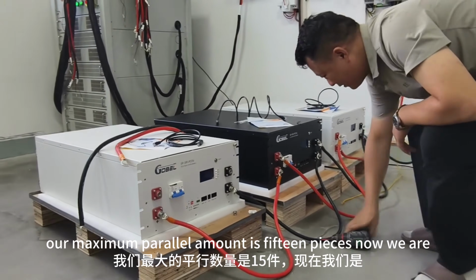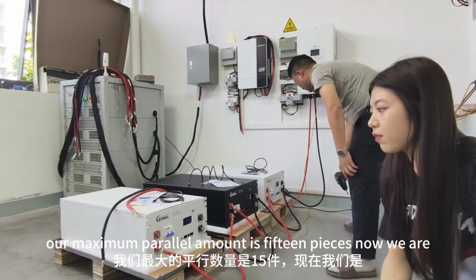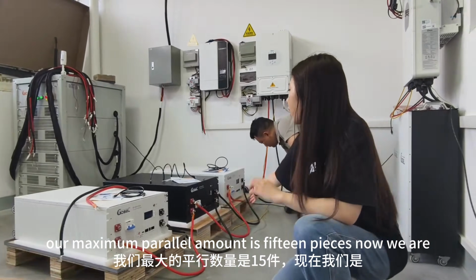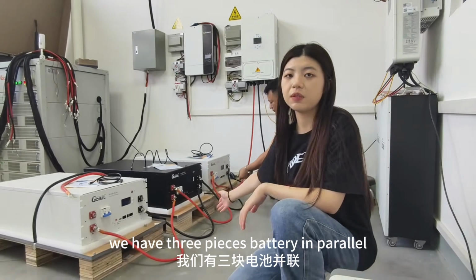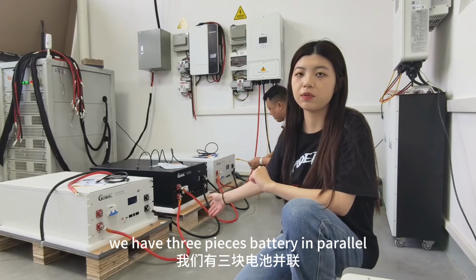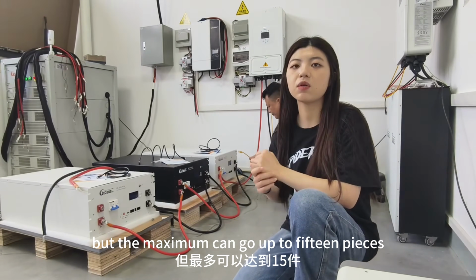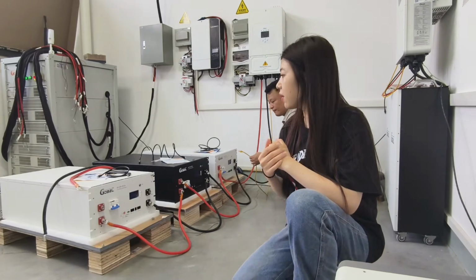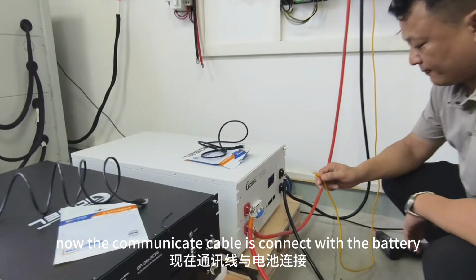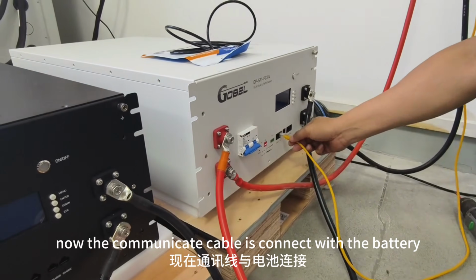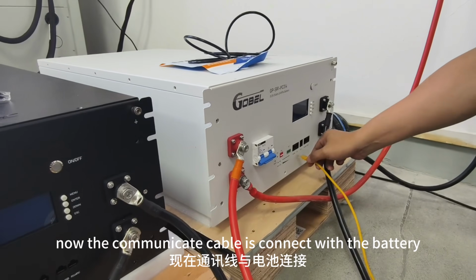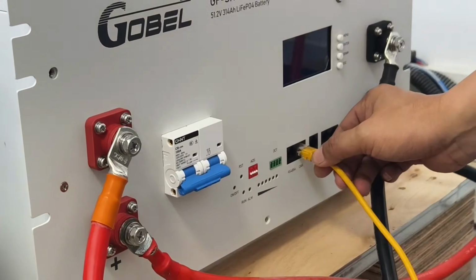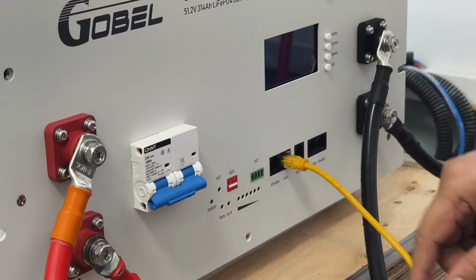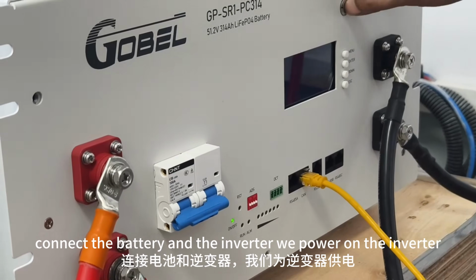Our maximum parallel amount is 15 pieces. Now we have 3 pieces of battery in parallel, but the maximum can go up to 15 pieces. Now the communication cable is connected with the battery's CAN port, connecting the battery and the inverter.